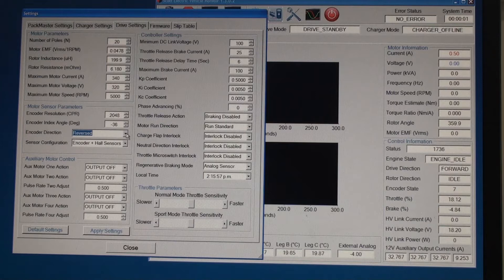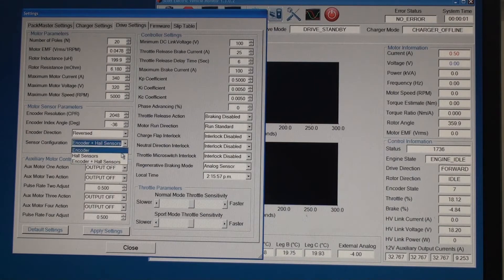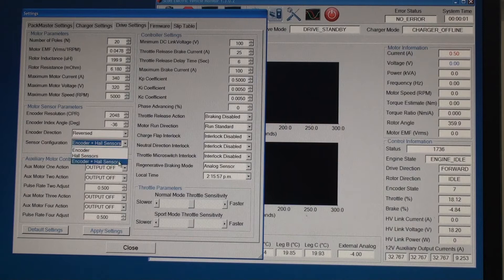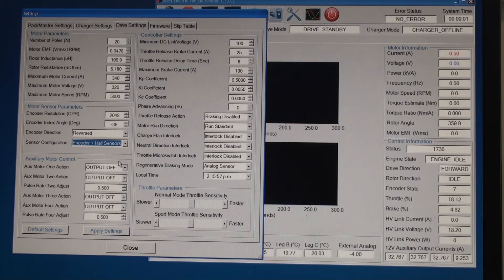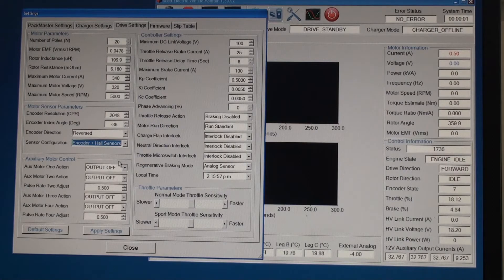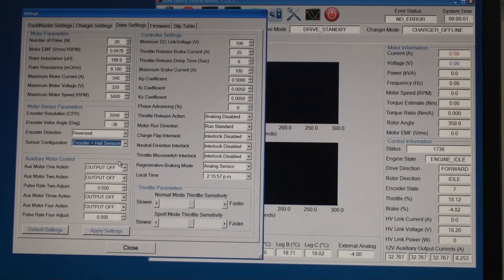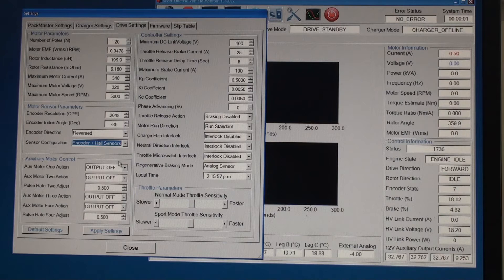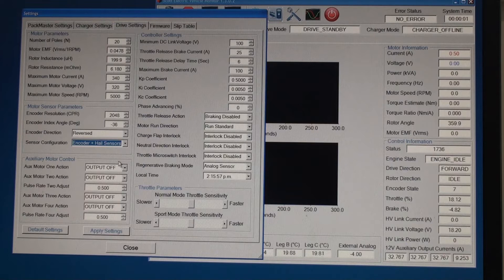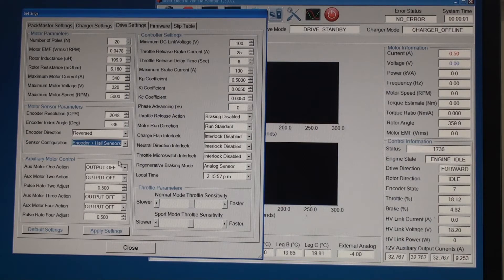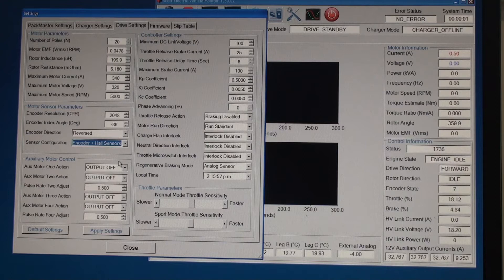The last setting we need to decide on is whether we're going to use Hall sensors or Hall sensors plus encoder to determine the rotor position. The SD100 is capable of just using Hall sensors to estimate the rotor position. Or we can use both the encoder and Hall sensors combined, which is what we're doing in this case. If the setting is set to encoder plus Hall sensors then the controller uses the Hall sensors to determine the initial rotor angle. And then once the first index pulse is received then the encoder is used as the primary rotor position sensor.